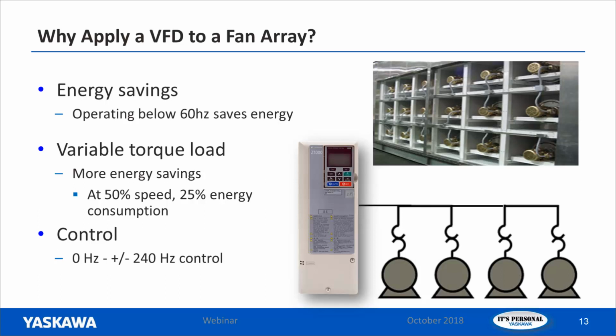The line voltage in America, whether it's 208, 230, 240, or 460, is always going to be pretty much at 60 hertz. And it's the frequency that determines the speed the motor is going to run, rather than voltage. So with everything being at 60 hertz, if you're just running the power to the motor, it's only going to spin at one speed, the 60 hertz. So being able to vary the speed is a big deal.